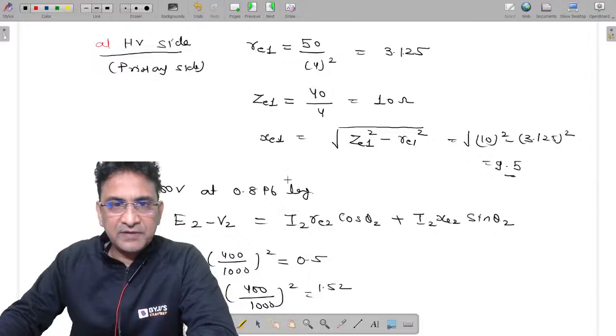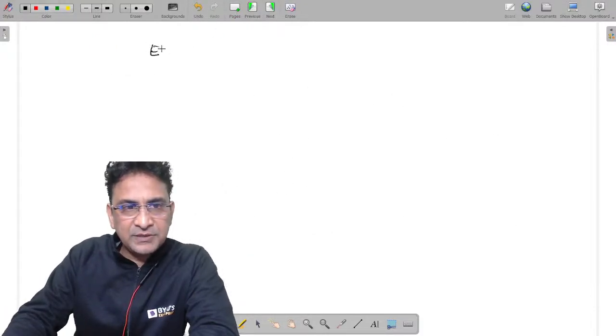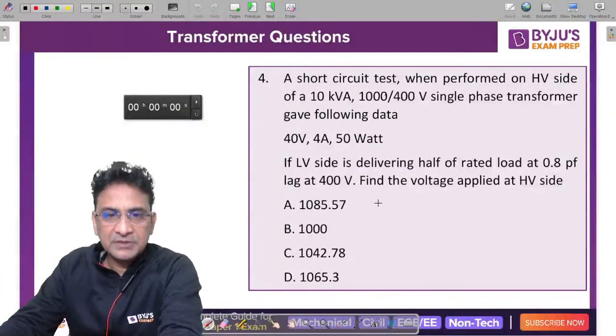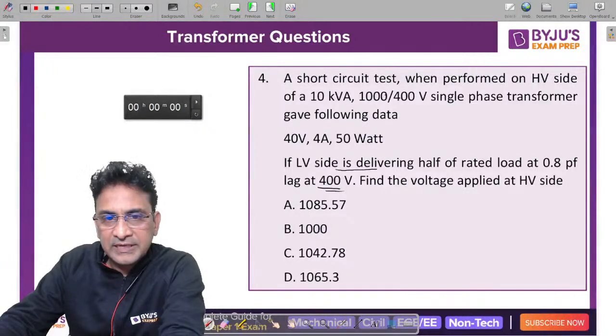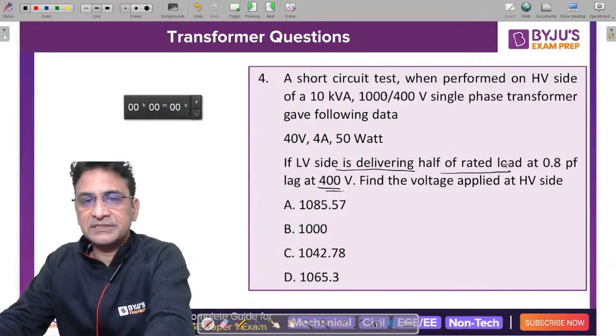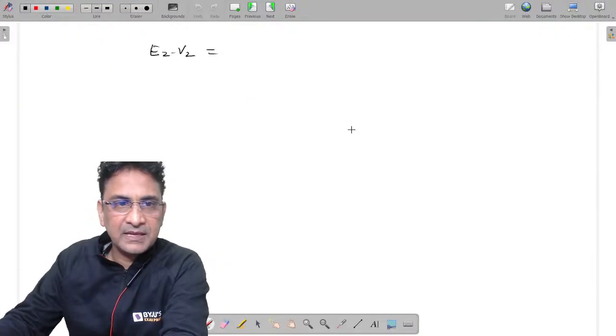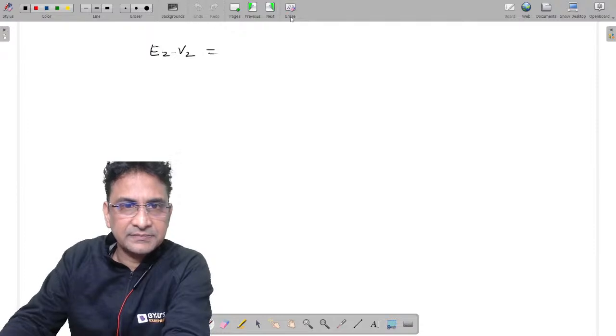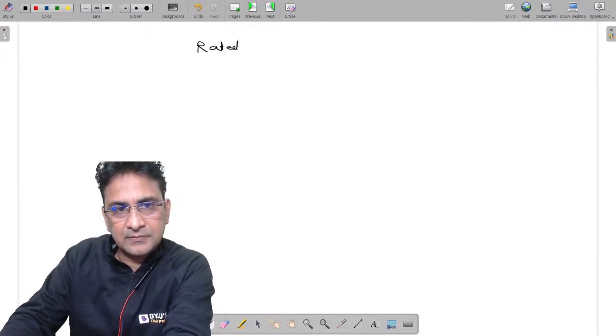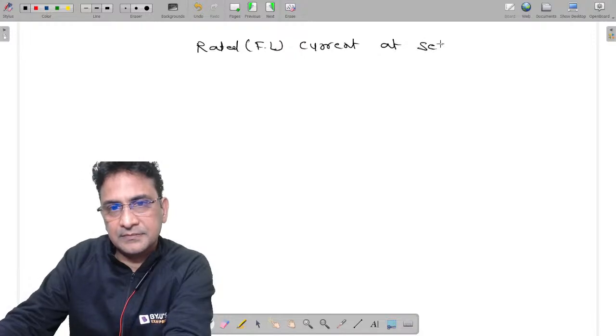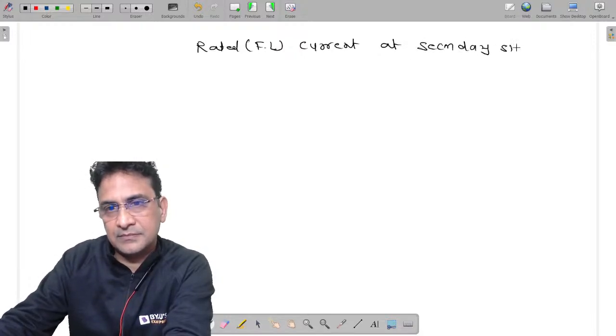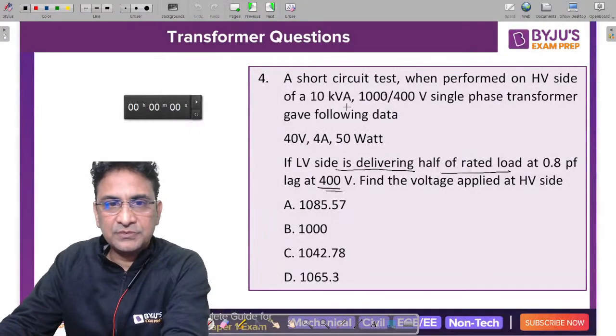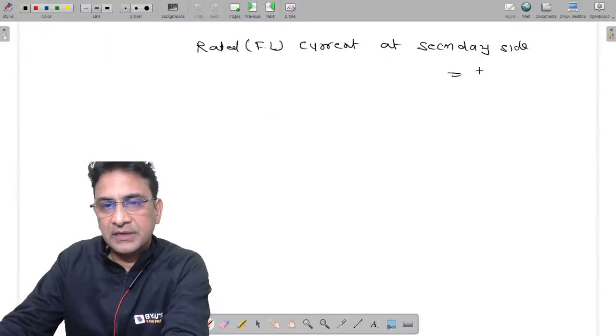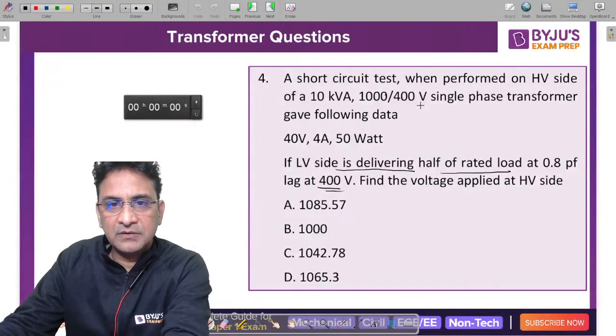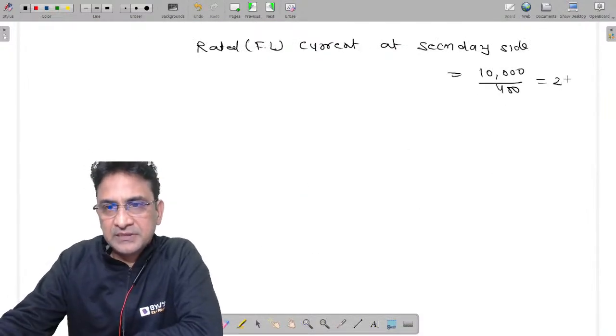So from these two data, we can find the value of E2 minus V2. So E2 minus V2, I2 Re2 cos theta 2. But this 400 volt we are getting at the low voltage side while delivering half of the rated load. The load is not the rated load, it is half of the rated load. So what is the rated current? First find the value of rated current, or full load current, at the secondary side. The kVA is 10 kVA. Voltage is 400 volt. 10 kVA divided by 400 volt. So 25 ampere is the full load current.